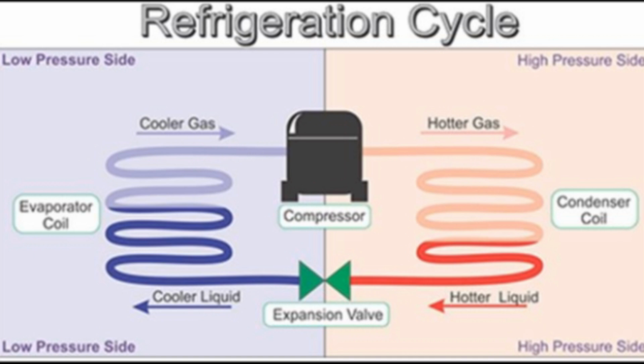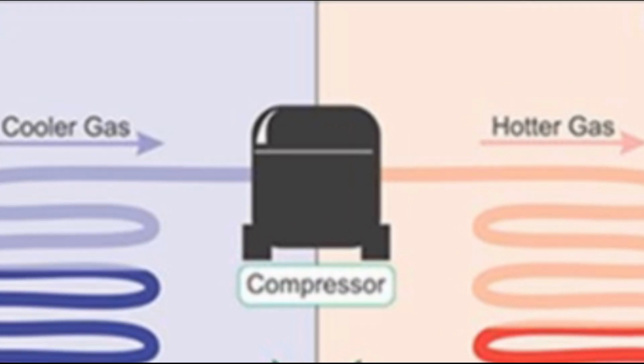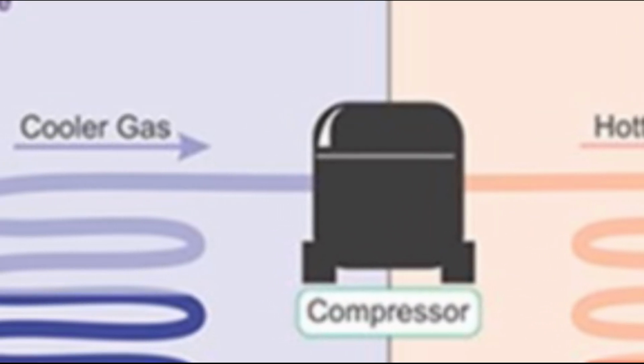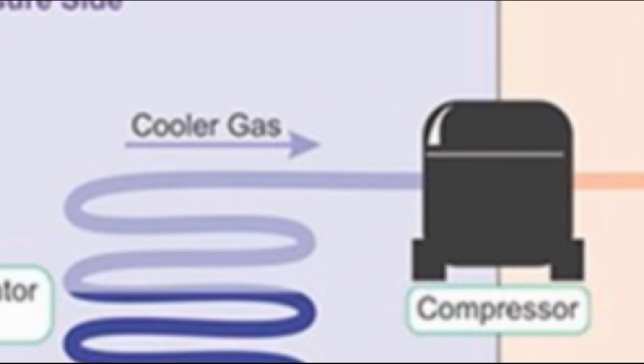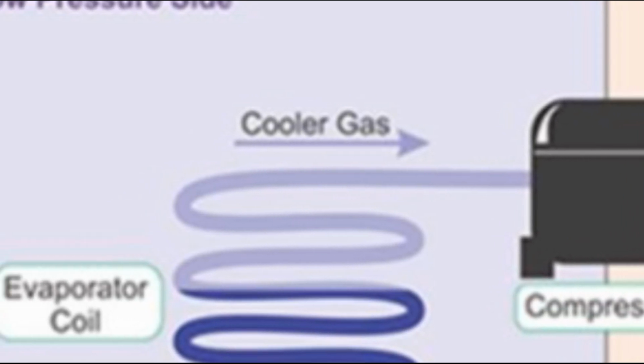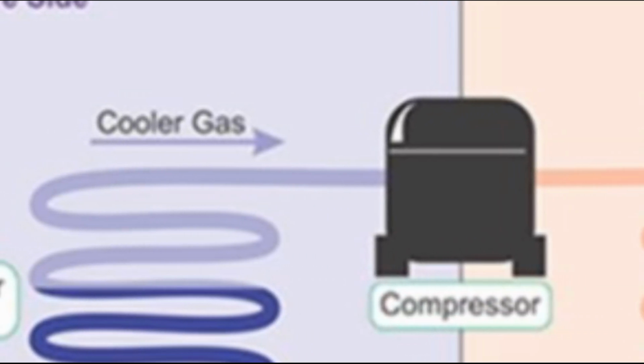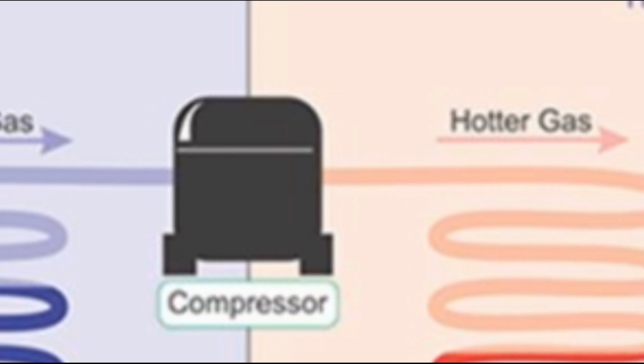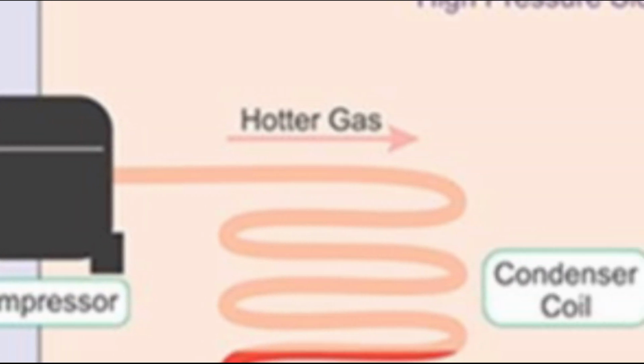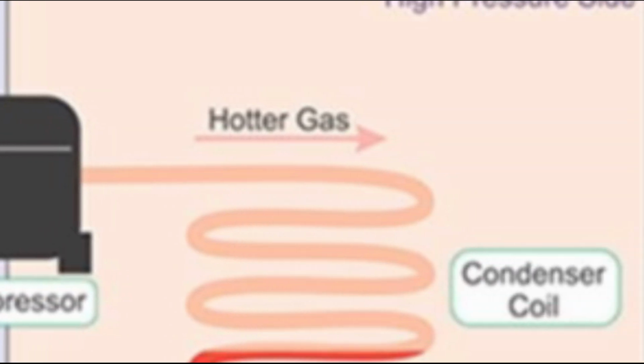As we increase pressure by reducing the amount of space allowed for something, in this case, our refrigerant, so too does our temperature increase. The increase is caused by our compressor. The compressor takes cold, low-pressure gas from the evaporator side of the system and pressurizes it by a substantial amount compared to the coil it came from. This increase in pressure heats it up, as well as increasing its boiling point.